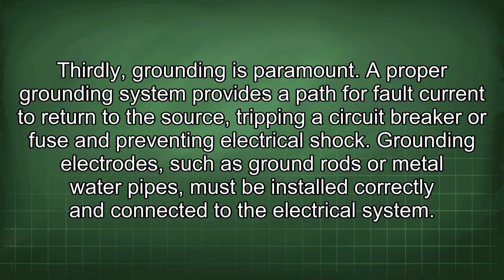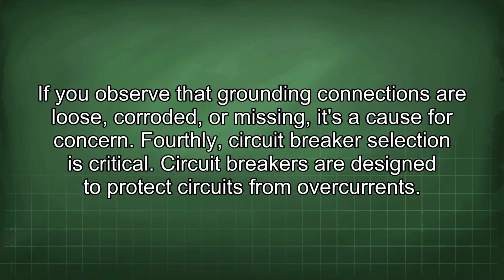A proper grounding system provides a path for fault current to return to the source, tripping a circuit breaker or fuse and preventing electrical shock. Grounding electrodes such as ground rods or metal water pipes must be installed correctly and connected to the electrical system. If you observe that grounding connections are loose, corroded, or missing, it's a cause for concern.